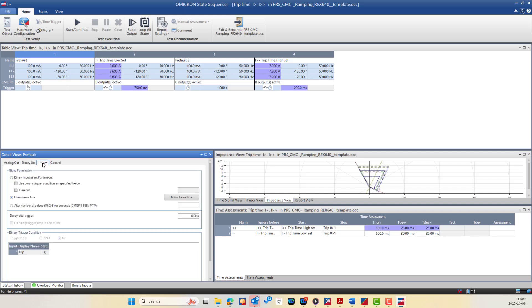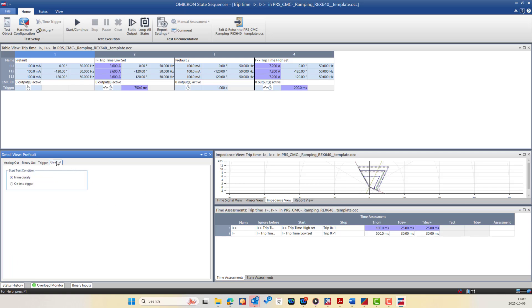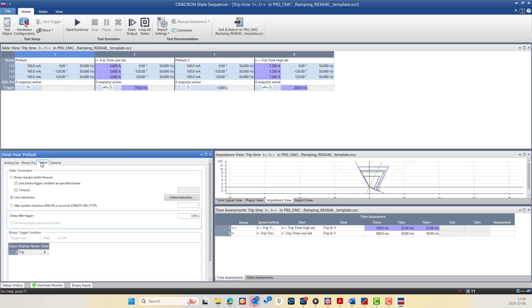We also have the Trigger tab, where you can set the transition condition between states, such as binary inputs or time delays. And we have the General tab, which allows you to synchronize the test start using GPS or IRIG-B and to start the test condition immediately or on a time trigger using the CMC GPS or IRIG-B pulses. This structure provides both flexibility and precision to simulate complex protection scenarios step by step.